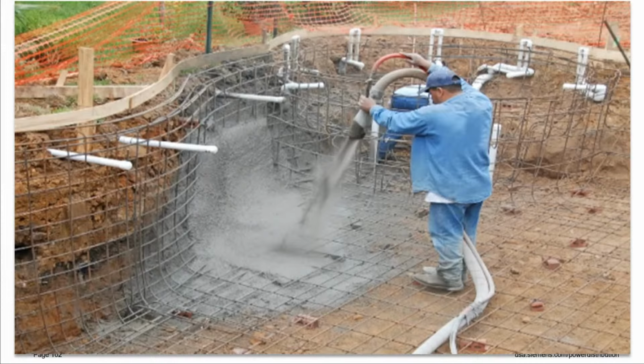before this was shot with the gunite, folks would take a piece of 8 gauge wire, maybe 4 foot, 6 foot, 8 foot long. One end of it is split bolted to a piece of rebar in that shell, at 4 points uniformly spaced around the pool, and the wire would just be left coiled up, laying out near the perimeter, laying out in the dirt for now. And then when they actually form the deck later, the perimeter surface, the other end of that 8 gauge.